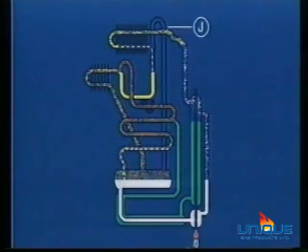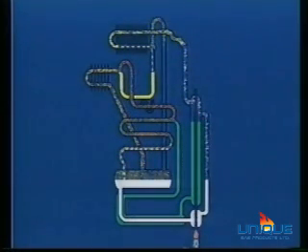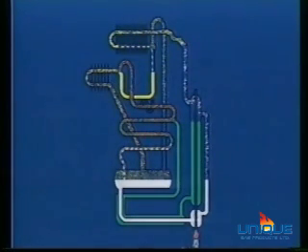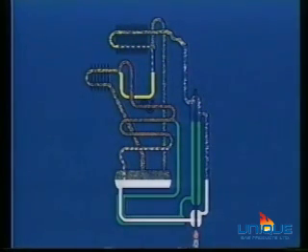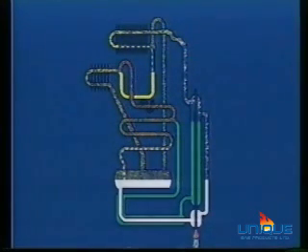Pipe J is the compensating tube. Its unique function is to enable the uncondensed ammonia vapor to return to the tank. This condition only occurs when ambient temperature is very high, or when the refrigerator is installed incorrectly.